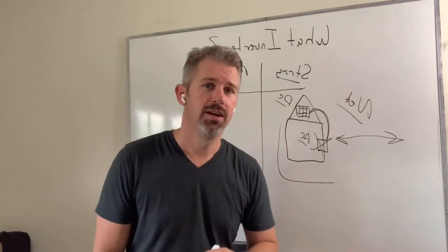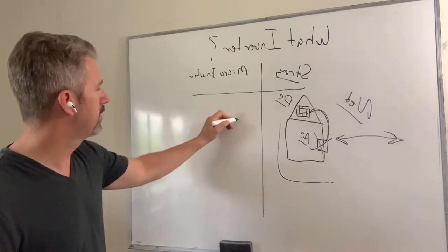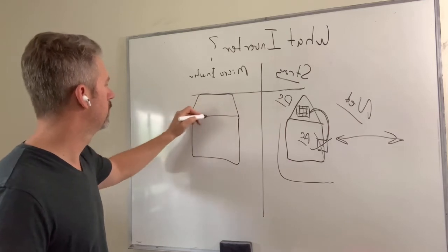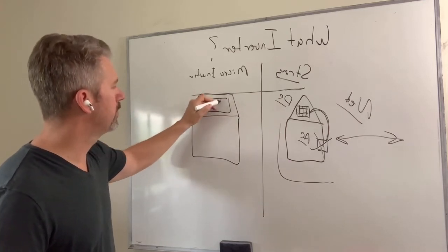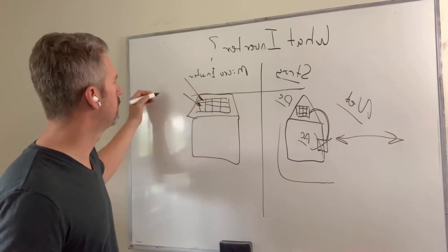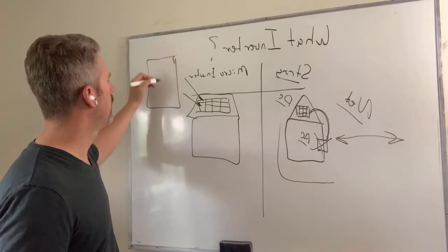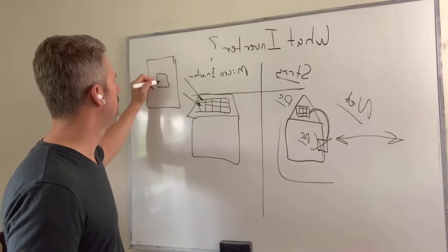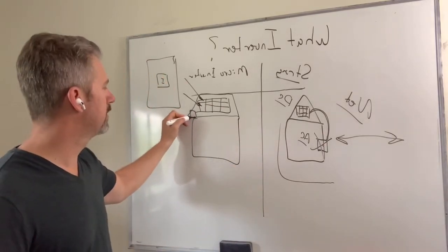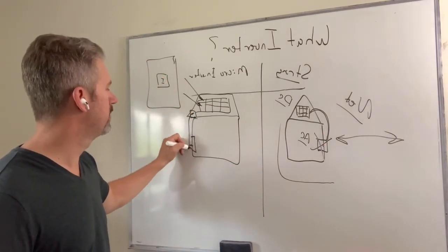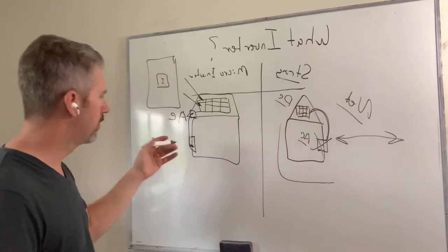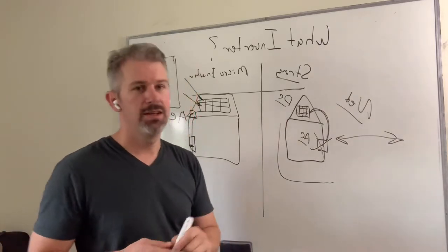Now, microinverters, they're a bit different. So you'll have your house, and you'll have your roof and your panels, but each panel will have its own inverter, right? So here's your panel. Right underneath it, there's going to be a mounted little microinverter, and all of those get strung together. There's going to be a combiner box on the side and a trunk that goes down straight into your AC panel. So it is AC off the roof going into your house.